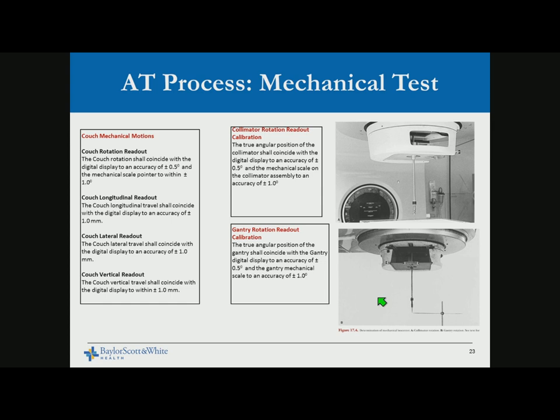Many of these mechanical tests are qualitative rather than quantitative. Historically, gantry rotation calibration is done with graph paper and a front pointer where you figure out the wobble — visually you just observe things. This is an issue because if tests are not quantitative, then after six months, a year, or three years following major upgrades, there is no way to quantitatively compare machine status from initial installation to the present.